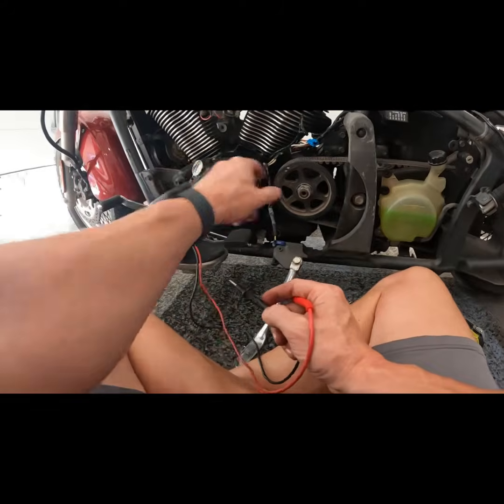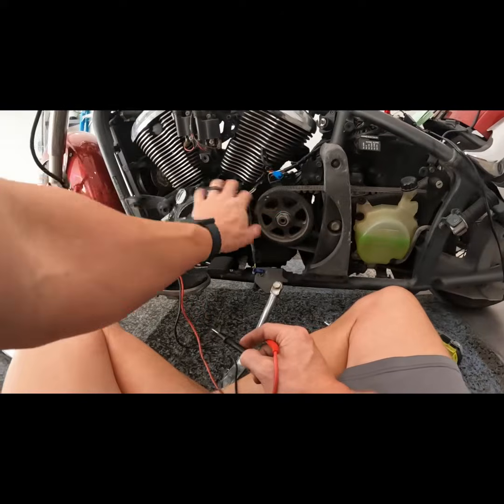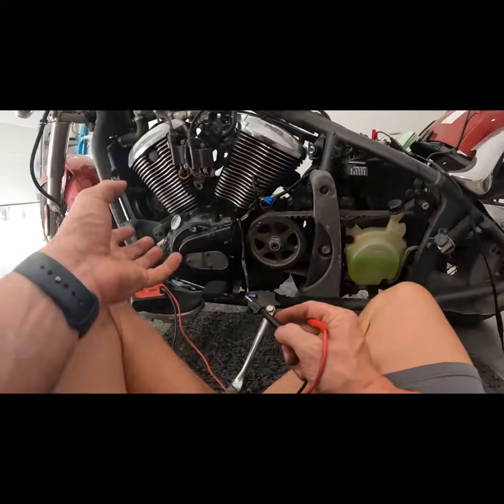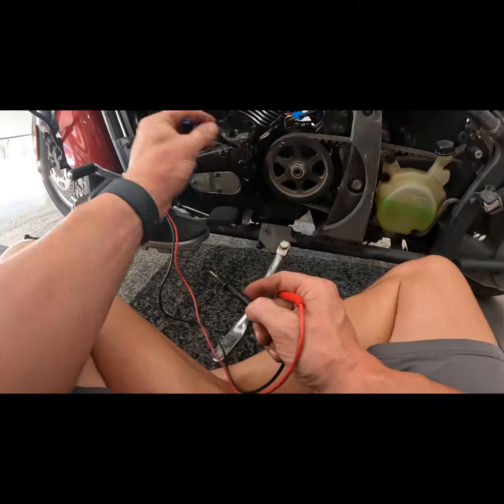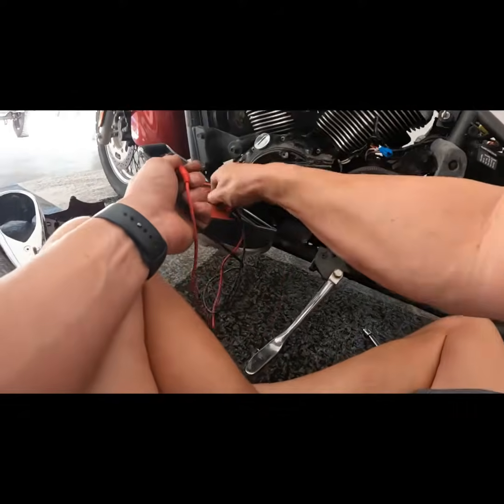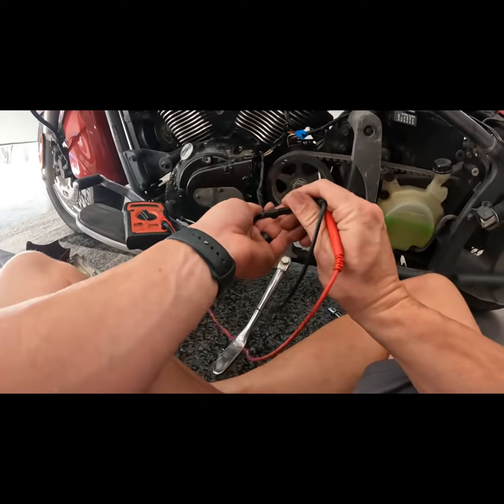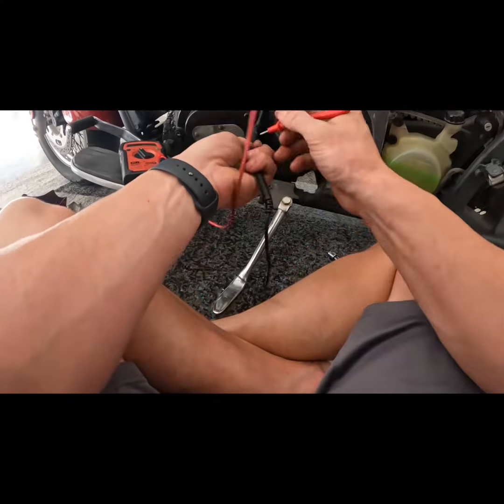So we want to go ahead and check this side of the system, because the problem could be coming from it and then we would have pulled this off for no reason. I do want to get an ohm reading on this sensor itself. So I'm going to change to the ohm setting, go ahead and check between these two posts.